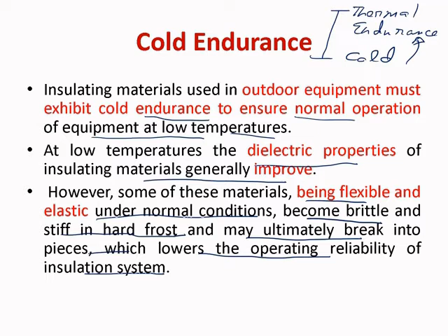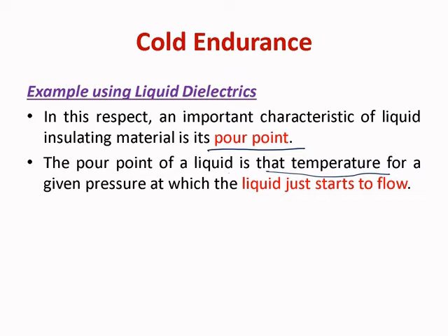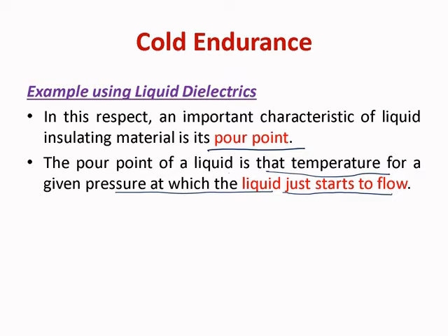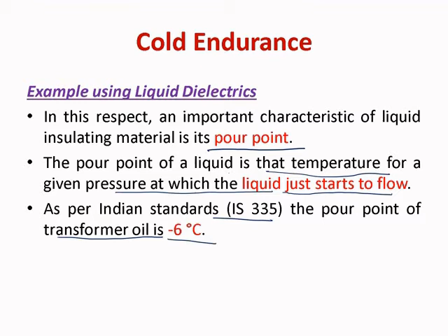Now, again, we want to explain these cold endurance properties with the help of liquid dielectrics. Generally, in the case of liquid dielectrics, cold endurance is characterized by pour point. Now, what is pour point? The pour point of a liquid insulating material is that temperature for a given pressure at which the liquid just starts to flow. It means that the liquid maintains its mobility up to this temperature. As per Indian standard IS 335, the pour point of the transformer oil is -6 degrees.